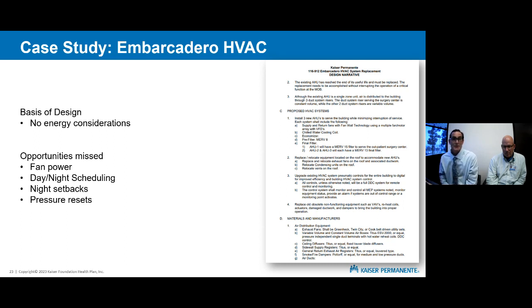There's a checklist of things that we now ask teams to do that just didn't get looked at here. Where is the fan power relative to our fan power benchmarks? What's happening at this air handling unit, daytime versus nighttime? Are we actually shutting down at night? Are we setting back at night? Are there pressure resets that we can do within the ductwork or any of that? So those are all opportunities that could have happened during a design narrative.